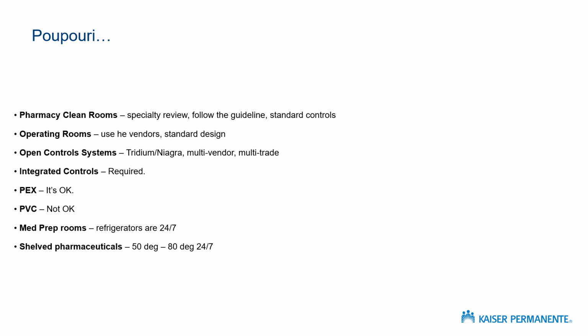PEX is okay. We're fine with PEX piping. We're using PEX piping in a lot of our potable water systems, even heating hot water systems. So we're fine with PEX piping, no problem. PVC piping is not okay. Kaiser Permanente has a ban on PVC piping from an environmental perspective, so we can't use that.